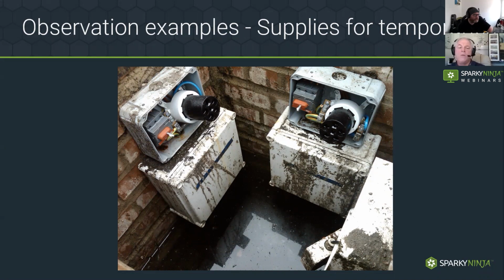So when we're looking at this sort of situation, we've got to do a thorough inspection - taking the cover off the bottom and inspecting the connection where the armour is terminated. We found that the gland, nut and everything was just rusted through. Cheers, Daniel, that's the sort of situation.